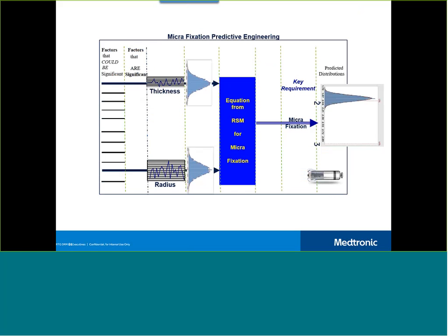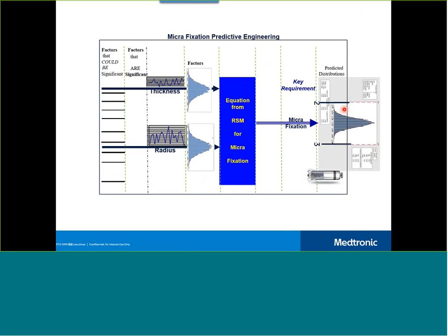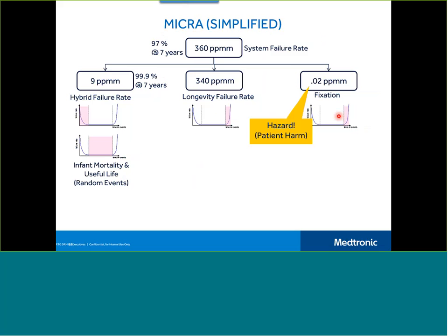That equation we got from that, we bring in the variation of thickness we were getting from manufacturing, the variation of radius of curvature we get from manufacturing, plug it through the equation, and predict what our distribution would be compared to our spec limits of 2 to 3 newtons. And you see, initially, the initial design would have been below the lower spec limit of 2, would not have been good for human usage. And so we optimized it, and you see over here, we were able to get really good Cpk and really high confidence in the fixation force being within the spec limits of 2 to 3 newtons.